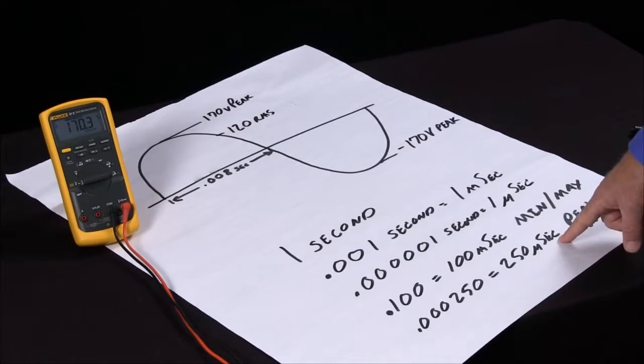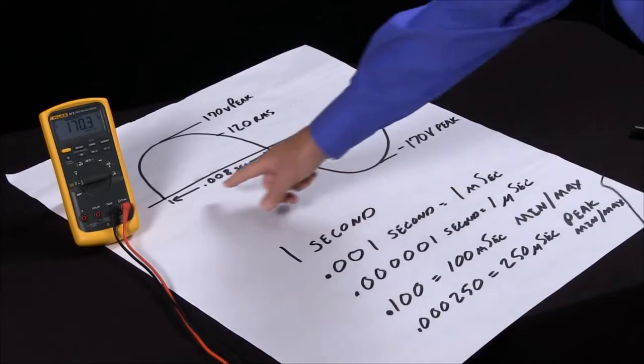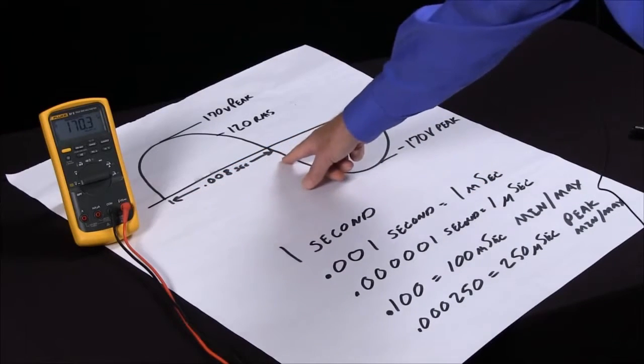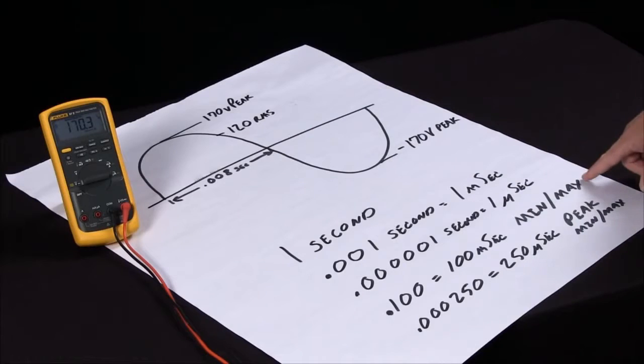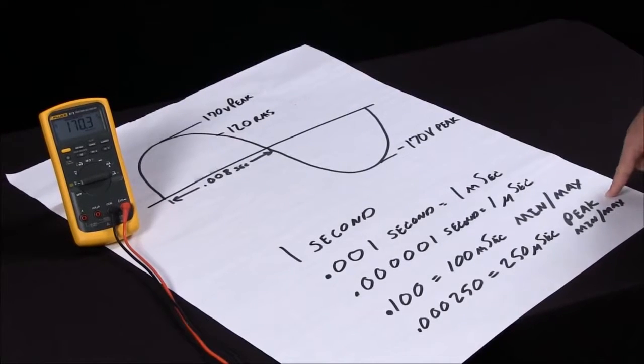When we work with a 60 hertz sine wave, half of that sine wave stretches eight milliseconds across. So my min max is not fast enough to capture transients, but the peak min max does give me that capability to capture electrical transients on different types of waveforms.